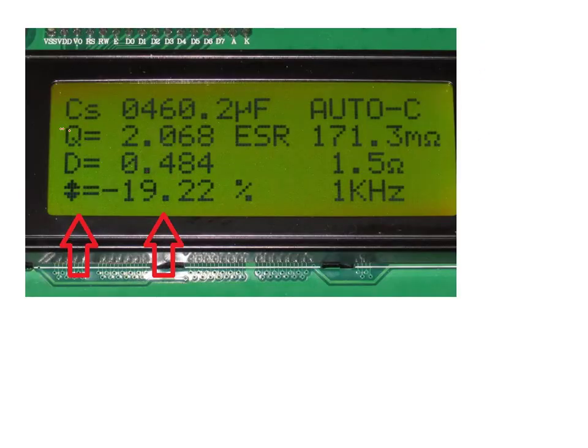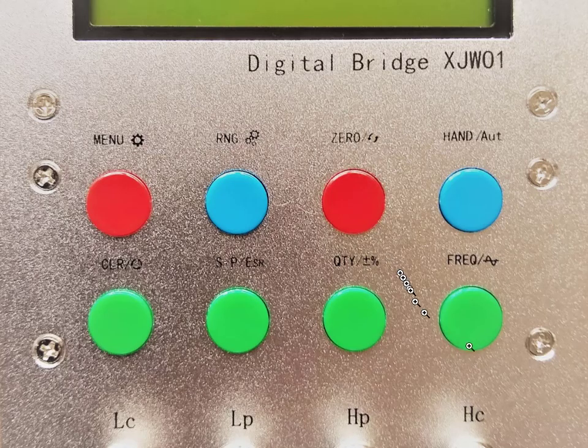So here's an example of it measuring a capacitance. It says CS for series mode, and auto C range. That's measuring the ESR it's giving you here, but the difference is the difference in the capacitance measurement between this and the first one that you measured when you press the Q button. And you can see that there's a double arrow here which is showing you the difference percentage between this and the first one that you measured. And then lastly we've got the frequency button, which changes the internal frequency used to measure the component under test.